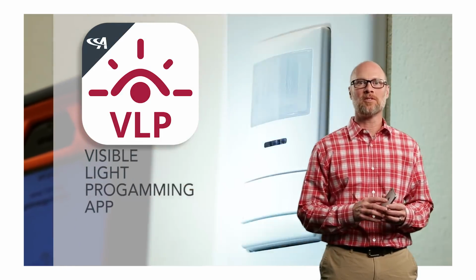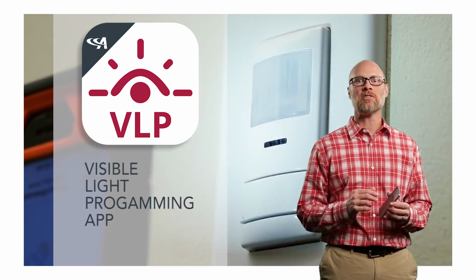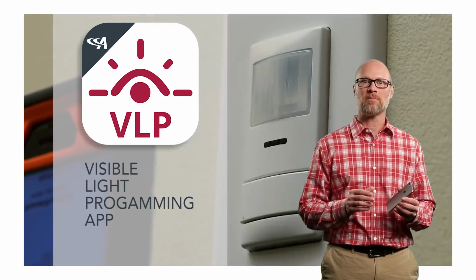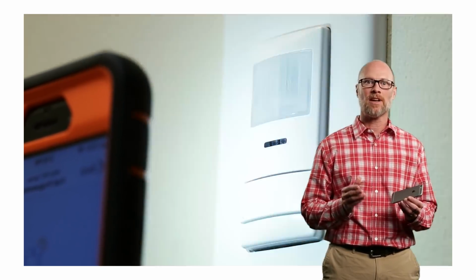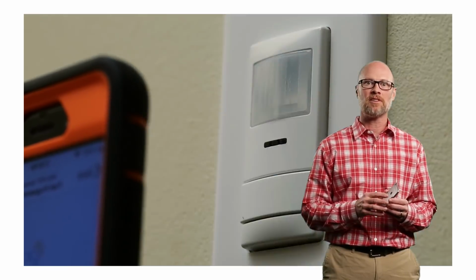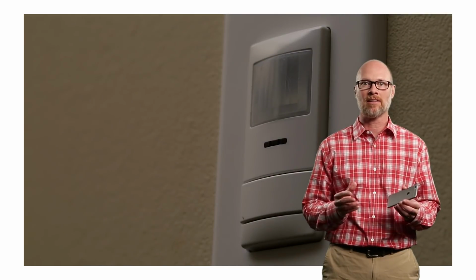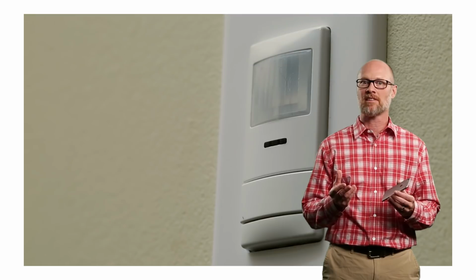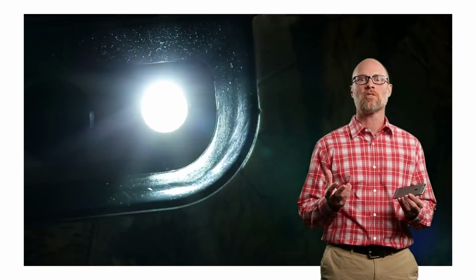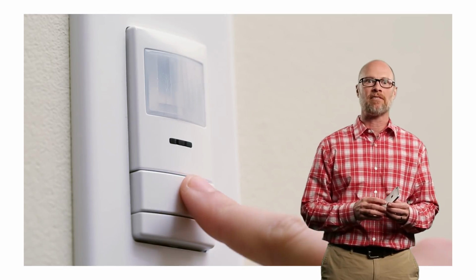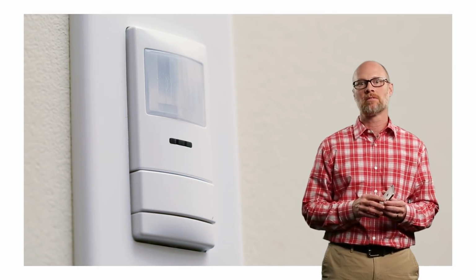VLP is short for Visible Light Programming, and it works by using the flash on your phone to communicate with the sensor. These flash pulses form a secure code that VLP-enabled sensors read as commands to change configuration settings. Think of it as kind of Morse code for sensors. This technology makes it quick and easy to modify sensor settings without having to set dip switches or navigate push-button programming, and that saves you time and money on the job.